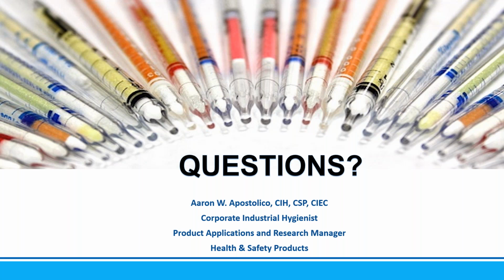And in doing so, you would want to record that down, as well as the correction factor that would be utilized, which you would find in the instruction sheet that comes with the box of tubes. So you would want to make sure that you have all of this information put together and then documented. And if you can accompany that with a picture of the tube, that's the best management practice. Awesome, thank you.